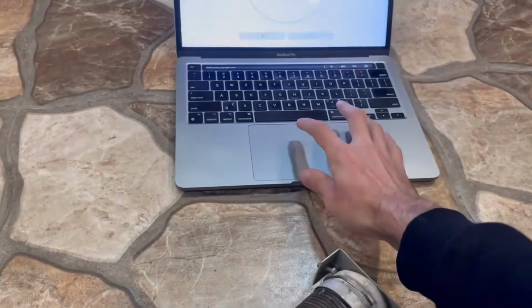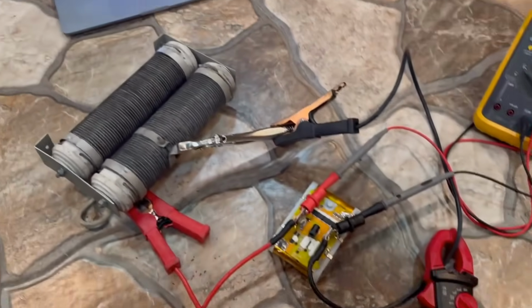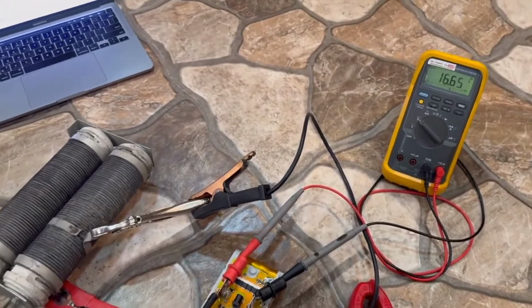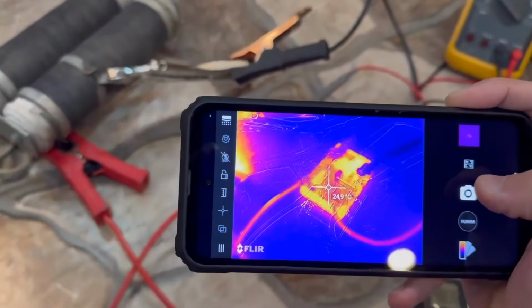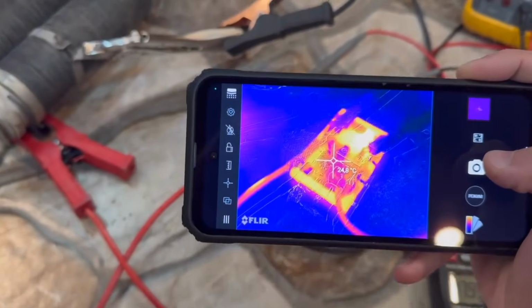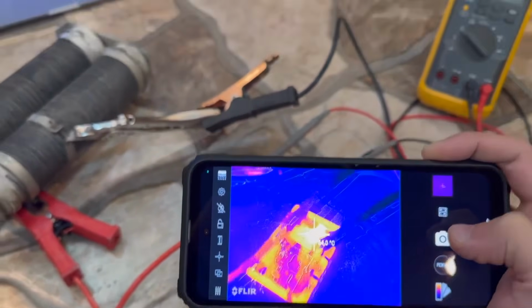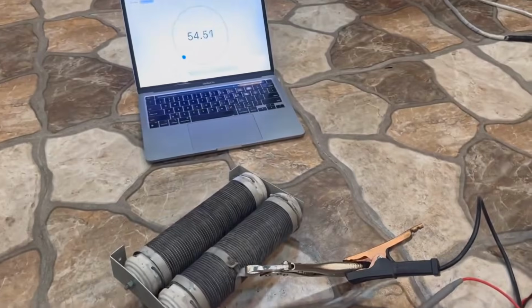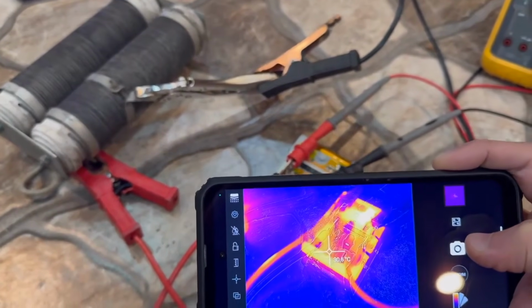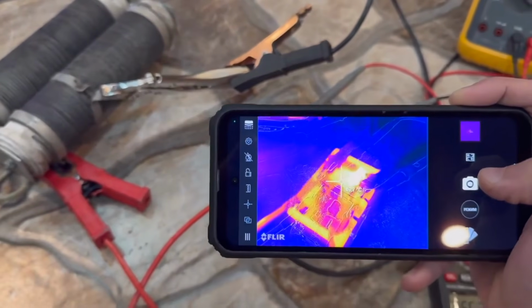At the same time, we're monitoring the temperature with a thermal imager. The temperature, of course, is pretty high, and it'll be even higher in a closed case. But nothing bad will happen, since we're not seeing any critical temperatures, and if anything does happen, the thermal protection will kick in. By the way, it works reliably. That was checked as well.